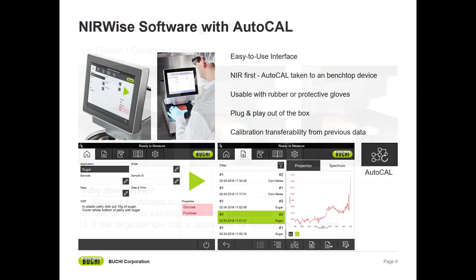My favorite feature is our ability to add new calibration points in just a few seconds. This can be performed by running a sample, highlighting the sample to mark it as a reference sample, inputting the known value, and then hitting the auto cal button. If you've ever worked with NIR chemometrics packages in the past, then you know that this process is significantly improved over third-party or external software options.